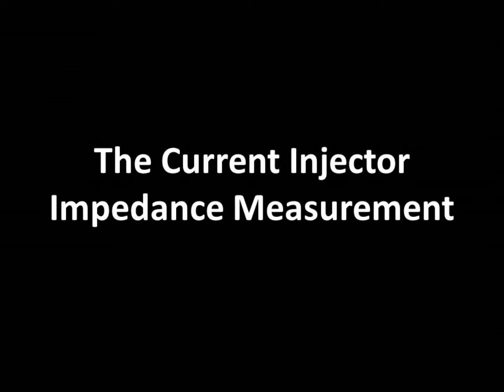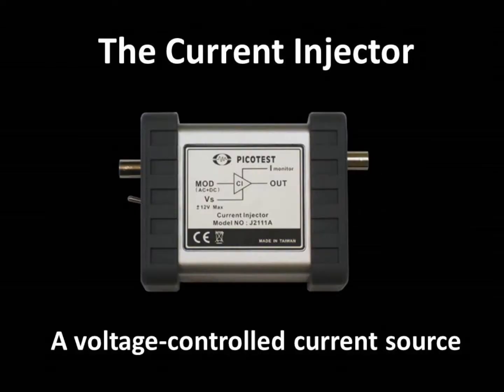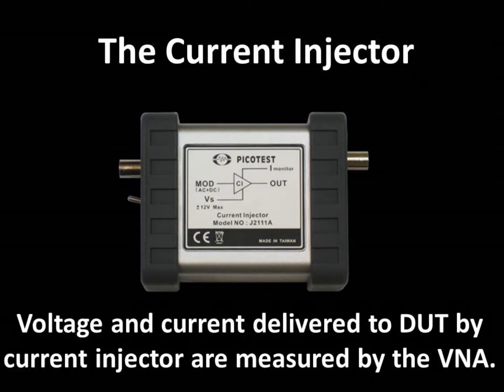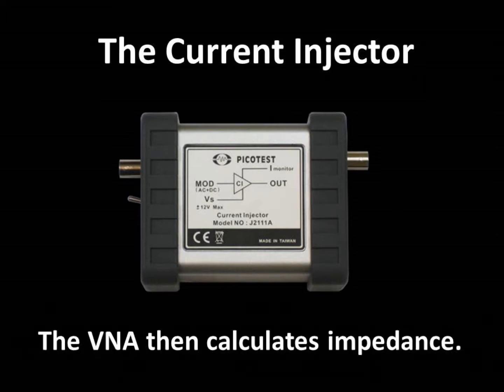The current injector is a voltage-controlled current source which is modulated by the VNA. The resulting voltage at the device under test, or DUT, and the modulated current are both measured by the analyzer, which then calculates voltage divided by current to obtain impedance.